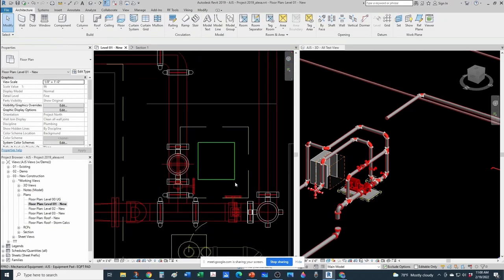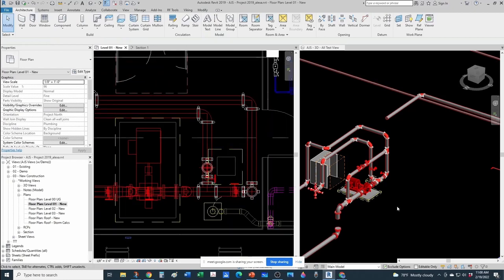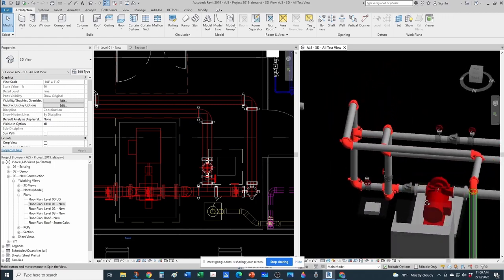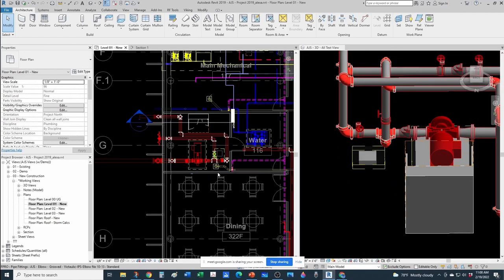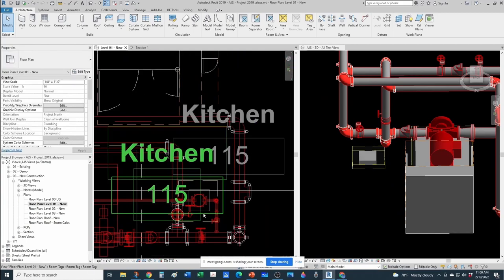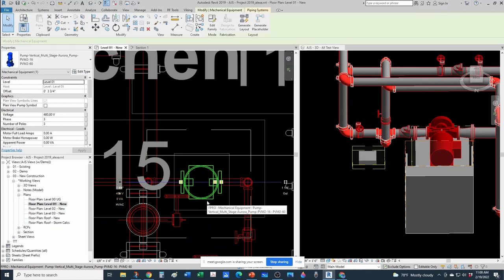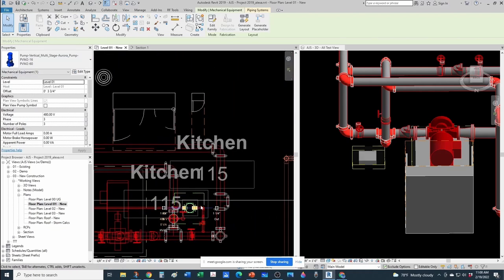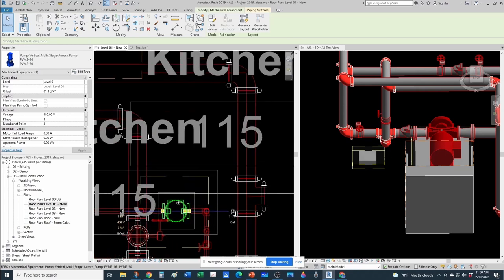We have our pressure maintenance or jockey pump that has to be sitting on top of that pad. Let me go to a different angle so I'm a little more comfortable. And those are vertical turbine pumps. In this case, yes, this is a vertical multi-stage Aurora pump, the PVM. This PVM series is very good. They have tons of different options to choose from. And you always want to select your jockey pump with a little higher pressure than your main fire pump. Because remember, the reason you have that pressure maintenance pump is to keep that pressure high, preventing the main pump from kicking in.